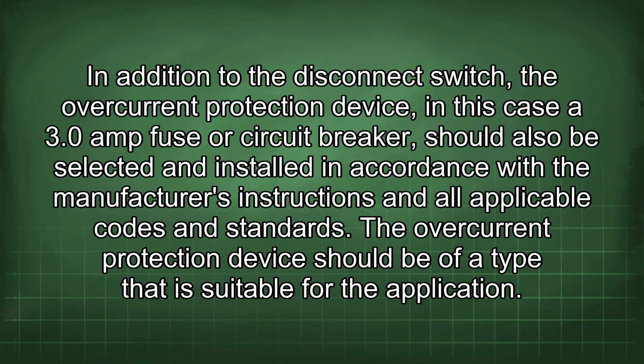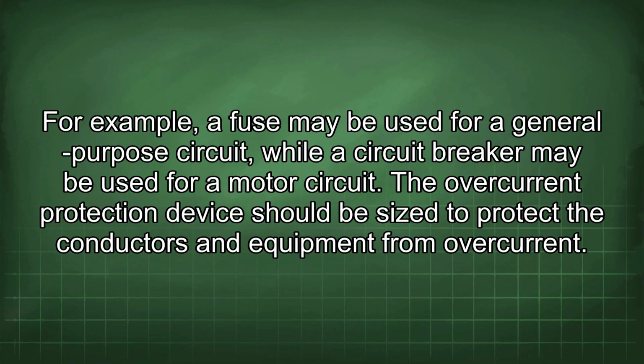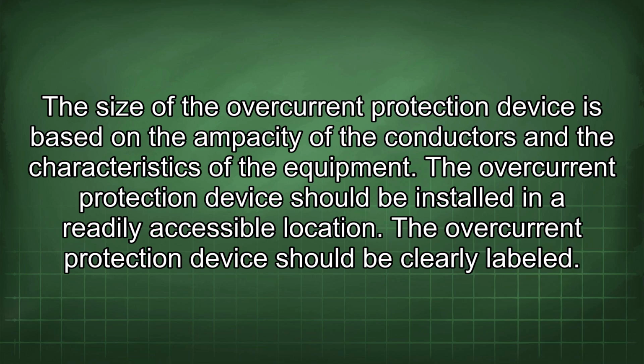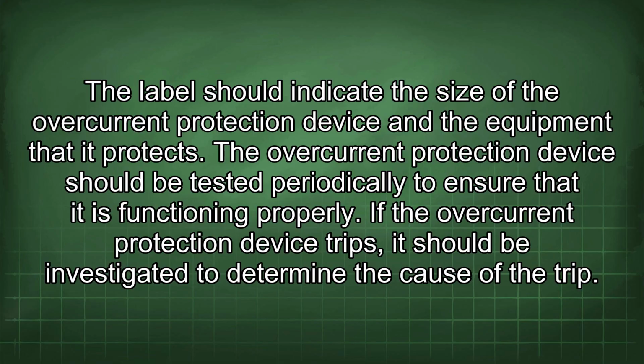The overcurrent protection device should be of a type that is suitable for the application. For example, a fuse may be used for a general-purpose circuit, while a circuit breaker may be used for a motor circuit. The overcurrent protection device should be sized to protect the conductors and equipment from overcurrent. The size of the overcurrent protection device is based on the ampacity of the conductors and the characteristics of the equipment. The overcurrent protection device should be installed in a readily accessible location. The overcurrent protection device should be clearly labeled. The label should indicate the size of the overcurrent protection device and the equipment that it protects.